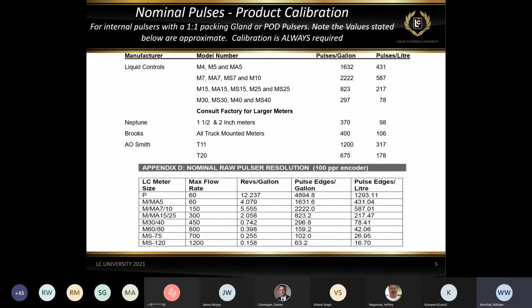Most of the electronic registers as they leave the factory will have a 1-to-1 packing gland gear ratio. Now, it's not to say that you can't use a 2-to-1. A lot of times on a mechanical to electronic retrofit, you'll see a 2-to-1 packing gland gear ratio on the mechanical meter. Well, you can use the same packing gland gear ratio, but what you're going to wind up doing is cutting that K factor in half, because we're actually going to be putting out fewer pulses per gallon. So just keep that in mind when you're doing retrofits.